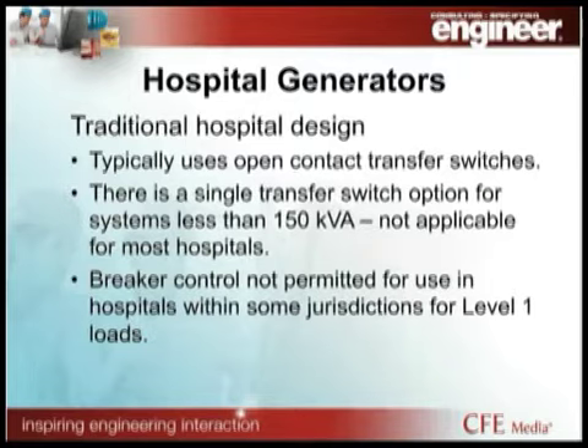So moving on, I'm going to base most of this presentation on what a traditional engineer is going to design. Traditionally, probably in the last 20, 30 years, we will use an open contact transfer switch. There is an option for less than 150 kVA that's permitted in the NEC to use a single transfer switch, but even in small hospitals, it's not considered a scalable solution. And plenty of jurisdictions, certainly I'm a resident in the state of Florida, do not permit that; the transfer switch is a breaker control type switch, or it is a traditional open contact switch.